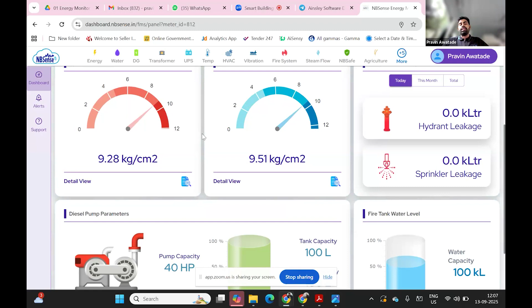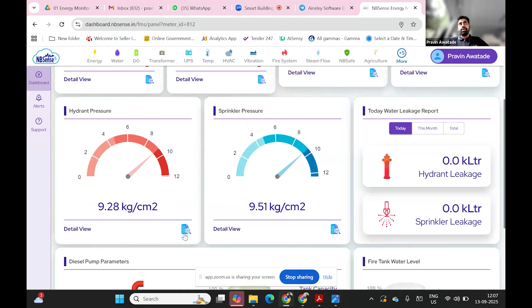Now the best part is the black box history. What the fire department exactly expects is this: figures show that in fire incident scenarios, 80% of the time your fire system was not functional. So the fire department wants to know whether it was really working or not. Before the incident, what was the status of your pump, your hydrant pressure, your diesel level, your fire tank water level. They want all this detail. This is only possible with IoT, because till the last moment it keeps giving data to the cloud.